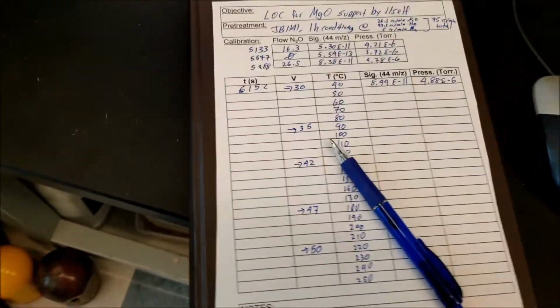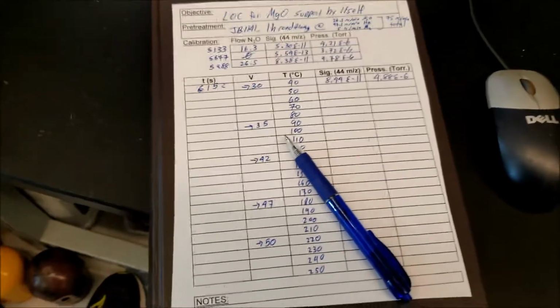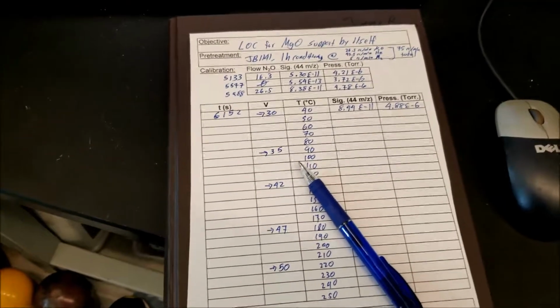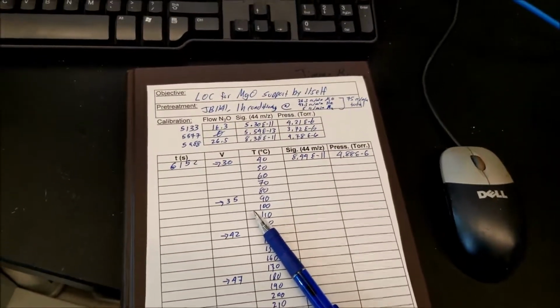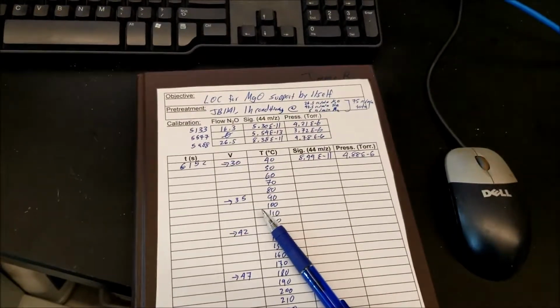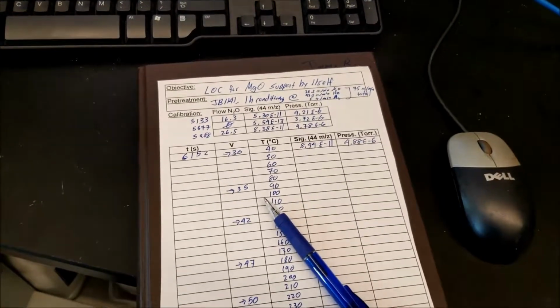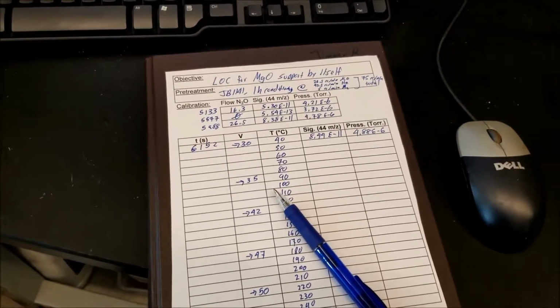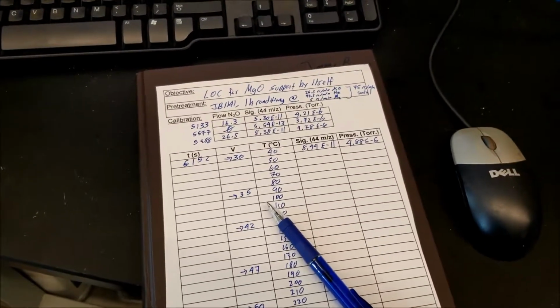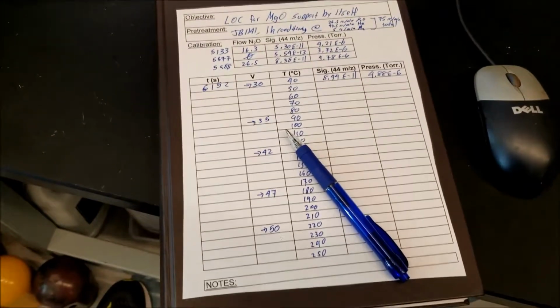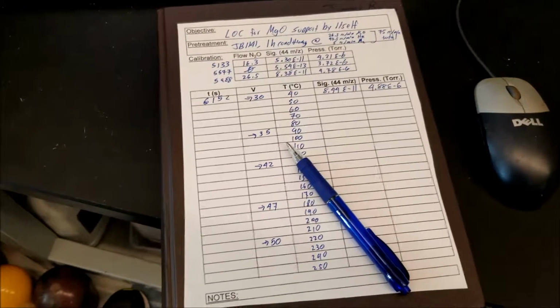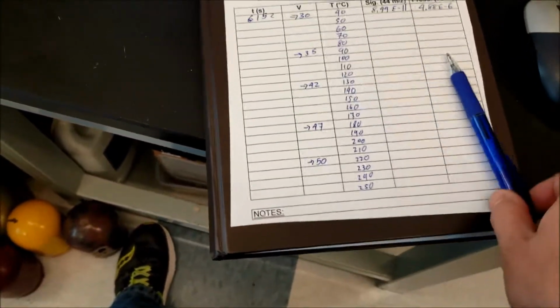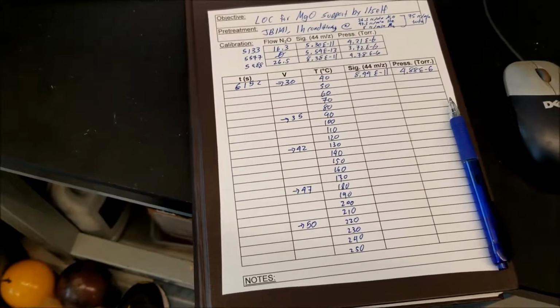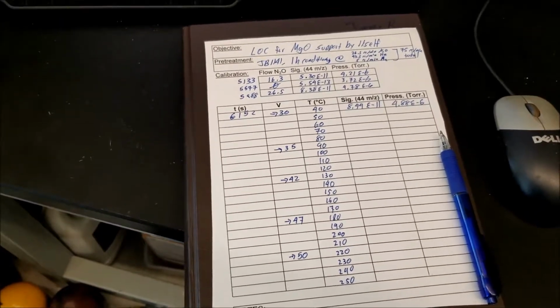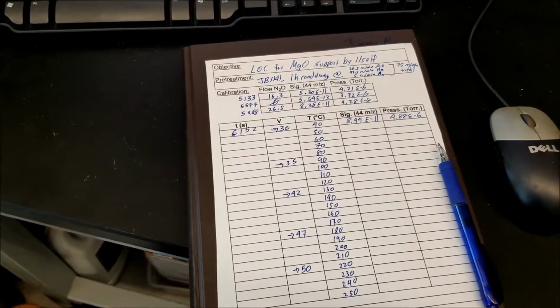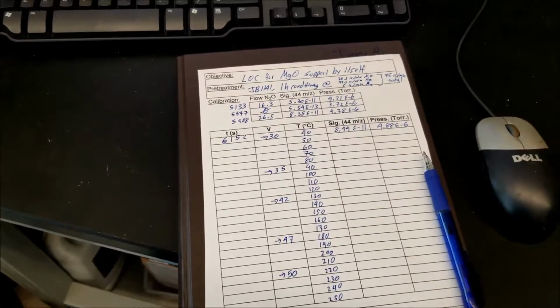I've gone through already and figured out which voltage settings, or when we have to increase the voltage setting, such that we're not heating the reactor faster than about 2.5 degrees a minute, 3 degrees a minute. And when we turn it up is when we'd have to wait longer than 5 minutes to go up the next 10 degrees, in case you're figuring out for yourself. But yeah, you do all the sample points up to 250 degrees, and then you can stop. If you want to go up to a higher temperature, you can. I would not go above, let's say, 350 degrees on this heating tape, because then you risk burning it out.